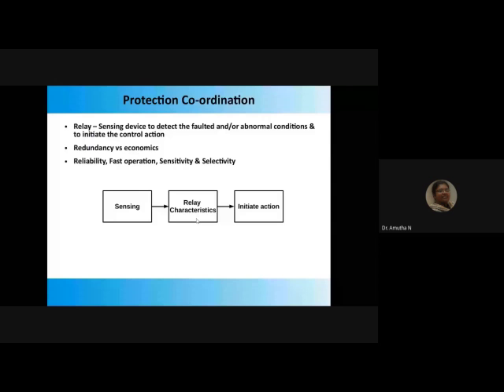The relay employed in this conventional grid should have properties of reliability, fast operation, sensitivity, and selectivity in identifying a particular fault location as well as characterizing the fault itself. It needs high selectivity as well as high sensitivity. Based on this predetermined relay characteristic, it tries to give the initiation action to the circuit breakers.